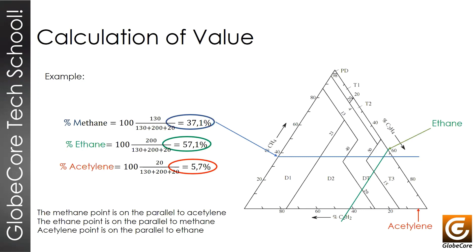If we plot everything correctly, we need to find the intersection of the three lines. This point identifies and where it lies on the triangle identifies the specific fault. In this case, we can say that we have fault type T3, the T3 fault for overheating. If we make a mistake while working with the system, we will not have a single intersection point. The points will not coincide. This may happen because we plot one of the lines incorrectly. If we don't get a single point, that is a very important indication that something went really wrong.